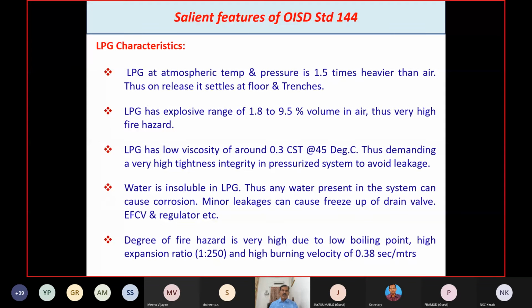LPG has low viscosity, around 0.3 cSt at 45 degrees centigrade, thus demanding very high integrity in pressurized systems to avoid leakage. That's why LPG pumps are given a double mechanical seal to prevent such leakages. And water is insoluble in LPG, thus any water present in the system can cause corrosion. Minor leakages can cause freeze-up of the drain valve and EFCV, external excess flow check valve, and regulator, etc. The degree of fire hazard is very high due to the low boiling point, high expansion ratio, that is 1:250, and high burning velocity of 0.38 meter per second.